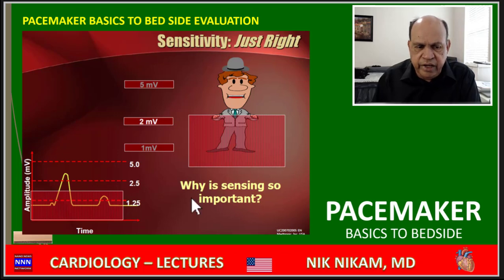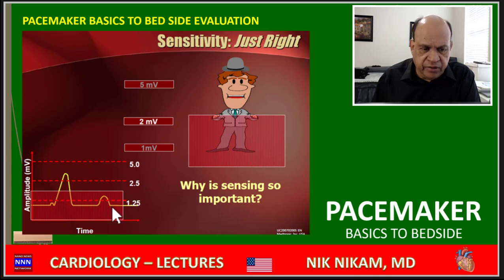The sensitivity in the atria is much lower compared to the sensitivity set for ventricular activity. For example, in the atria we may say, if you see any signal of 1.25 or greater, consider that atrial activity, meaning the atria are working, so you don't need to fire another beat on top of that. Whereas in the ventricle, it may be much higher, like 5 to 10.